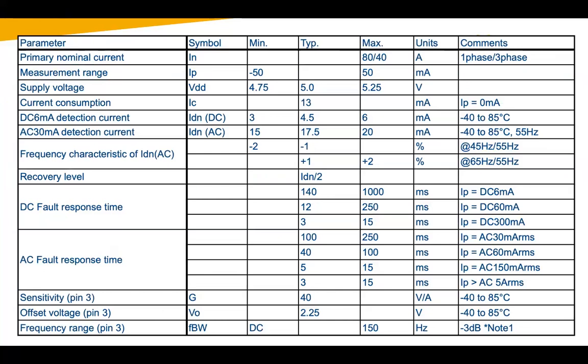A little bit more about parameters. I don't go into every detail, but here you can see in the middle of the screen the DC fault response times and AC fault response times. The AC clearly adapts 100% to the IEC and the UL standard, and the DC level also adapts to the IEC standard for electric charging of electric vehicles. You can also see the ambient temperature requirement, where it's working, from minus 40 to 85 degrees C, which should support most of the applications around. Even if it's hot on the board, our expectation is not more than 65 degrees C at board level, including all the heat rise of components and the ambient temperature. So it should be satisfied.